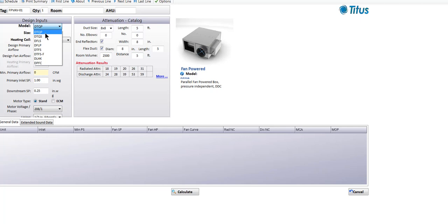When parallel boxes are in the cooling mode, they basically behave like a single duct VAV box. Since the fan's not running and we don't want to lose primary air to the ceiling plenum, parallel fan boxes are always equipped with a backdraft damper that closes to seal off the blower so that primary air can't leak out through the blower into the ceiling plenum.